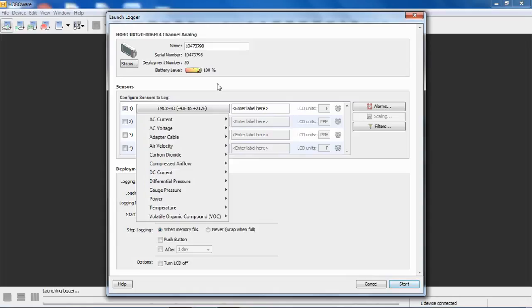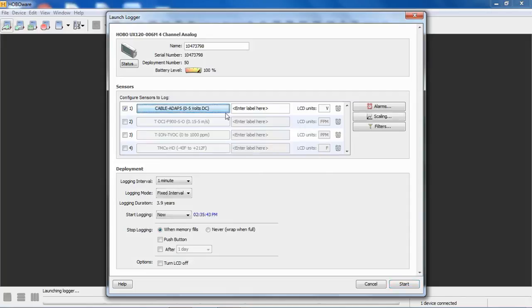If they are an Onset supported or supplied sensor, there's no scaling required. It's already applied, so you can see the scaling is grayed out. The ones where you'd have to apply linear scaling is to any of the adapter cables. So again, the adapter cables are just voltage dividers, or there's a shunt resistor on the 4 to 20 milliamp cable that converts that input to 0 to 2.5 volts, which is the native input to this logger. So let's select the cable adapt 5, which is a 0 to 5 volt input, since we used that in our analogy earlier. And you can see now that I've selected cable adapt 5, I have my scaling button available.